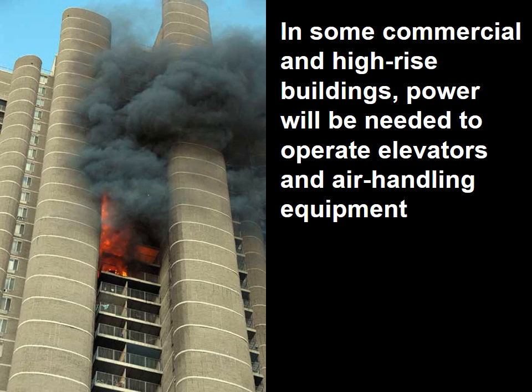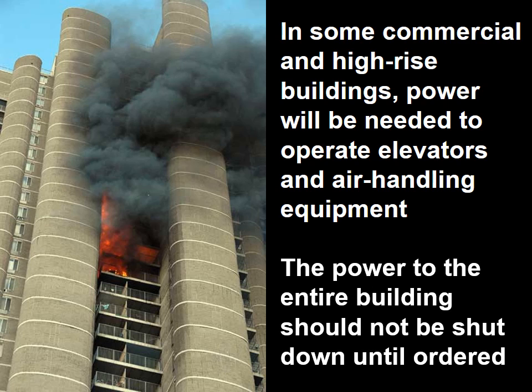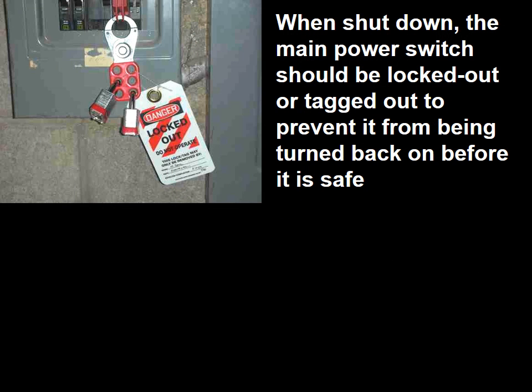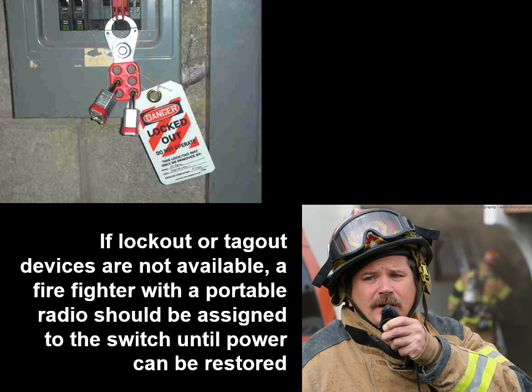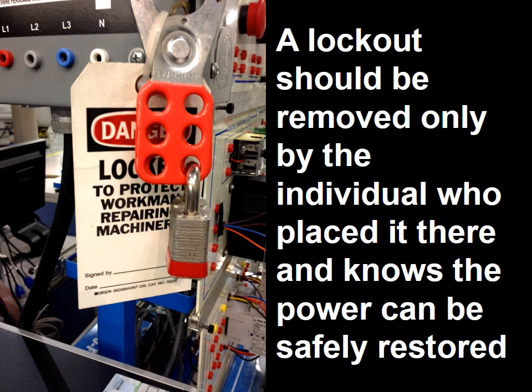In some commercial and high-rise buildings, power will be needed to operate elevators and air handling equipment. The power to the entire building should not be shut down until ordered. When shut down, the main power switch should be locked out or tagged out to prevent it from being turned back on before it is safe. If locked out or tagged out devices are not available, a firefighter with a portable radio should be assigned to the switch until the power can be restored. A lockout should only be removed by the individual who placed it there and knows the power can safely be restored.